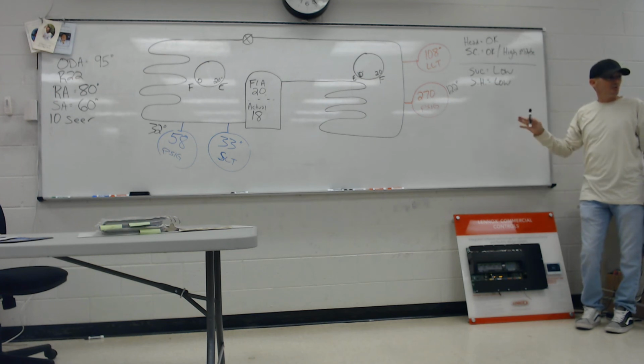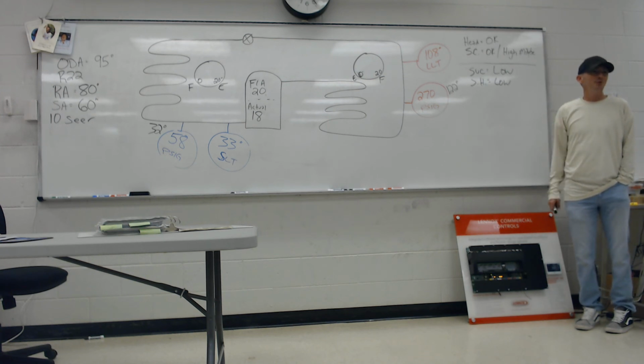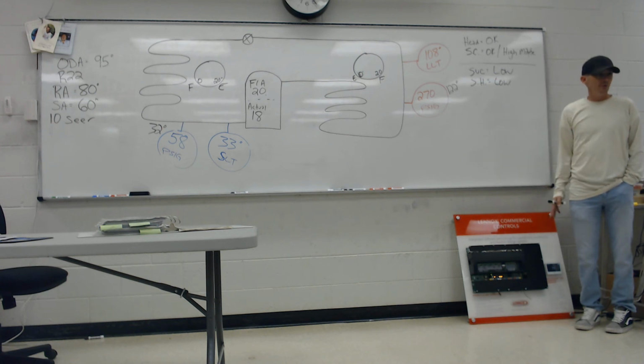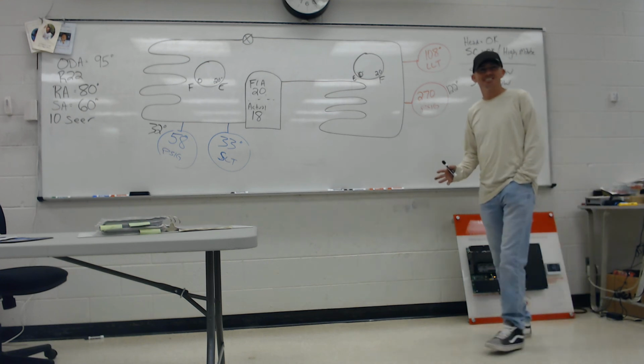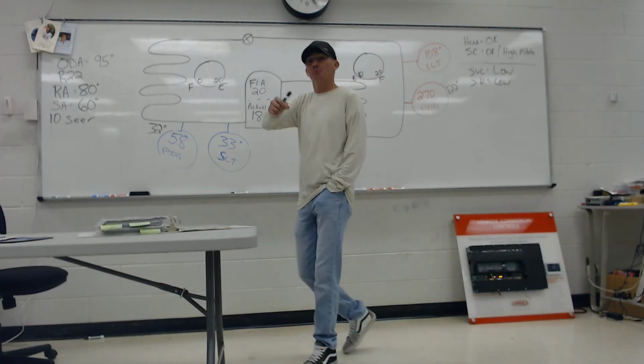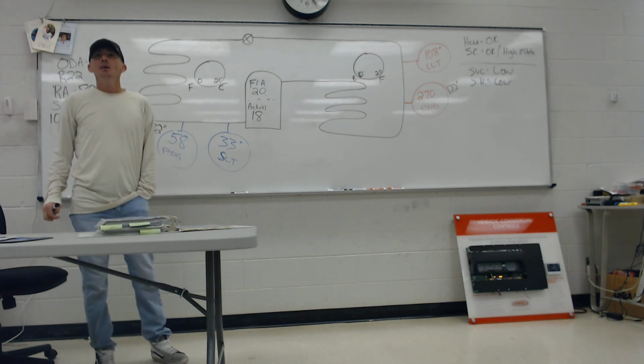Low suction, low superheat is always airflow. It's always airflow. I cannot stress this enough. Airflow, airflow, airflow. Airflow, boys. If you look at the back of that paper, I gave you a cheat sheet for different duct sizes and stuff like that.